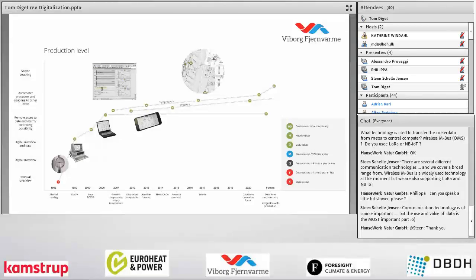In 2007, we got an automated process for the supply temperature that used the outside temperature to set the supply temperature. This has gotten more and more features, like a weather forecast, an add-on temperature based on flow, and an add-on temperature based on the time of day, so that we can compensate before peak hours.